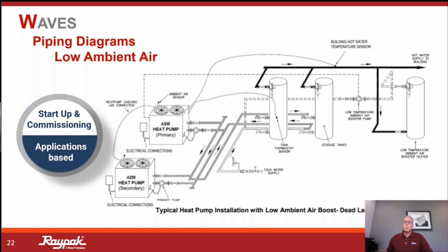I have another question. Sure, go ahead. So if you are turning it off to the heat pumps and you're in an area, well, you could have it so you have most of the area hot, but you're in actually a freeze zone. Don't you want to keep some running to keep the heat pumps from freezing inside? At least run them at a lower level. Right, and that's an excellent statement, Brian, and I like your choice of words because then we're going to talk about a defrost cycle. And yes, I want to make a distinction where the unit might hit this defrost cycle, and yes, it would take the circulator's operation, but at that point, it's more about the function of defrost rather than BTU production trying to reload a storage tank. Does that make sense? Yes.